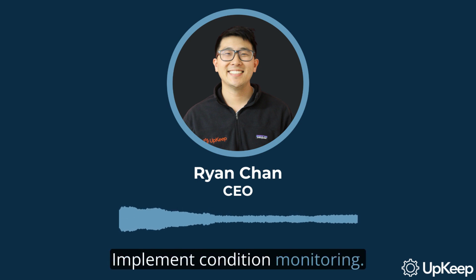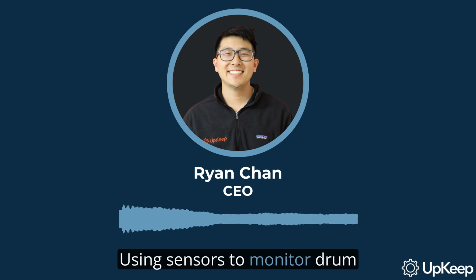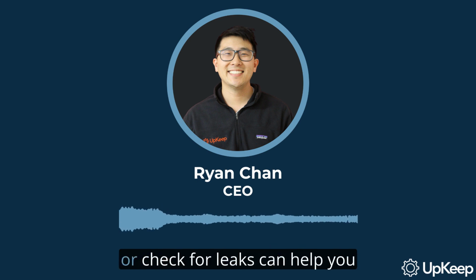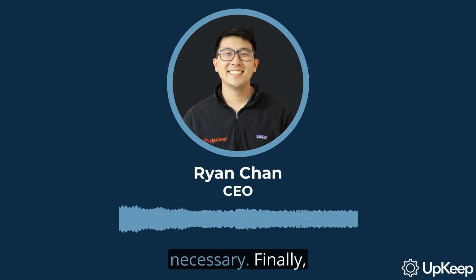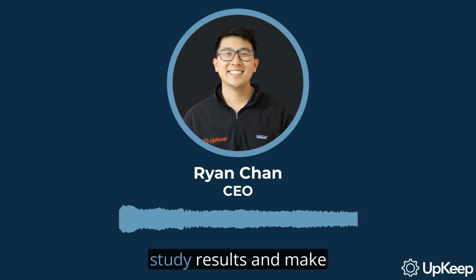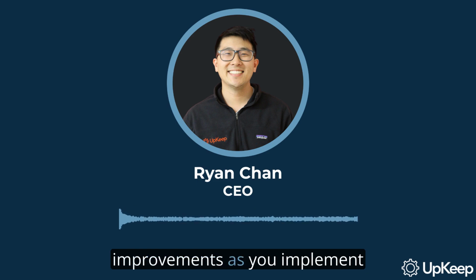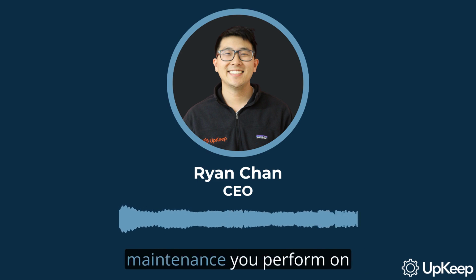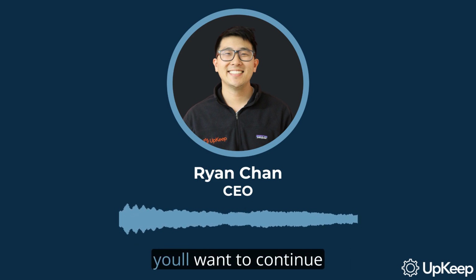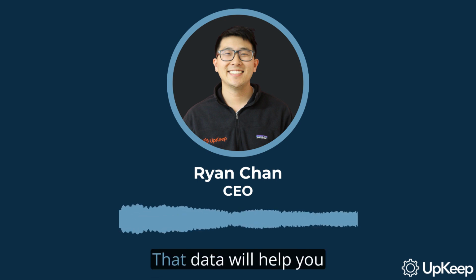Implement condition monitoring. Using sensors to monitor drum pressure, track temperatures, or check for leaks can help you make sure PMs are performed only when they're strictly necessary. Finally, study results and make improvements. As you implement changes in the preventive maintenance you perform on your boiler systems, you'll want to continue tracking data. That data will help you determine what kinds of impacts your changes have. Remember, the goal is consistent improvement here, so a one-and-done solution isn't likely going to be the best approach.